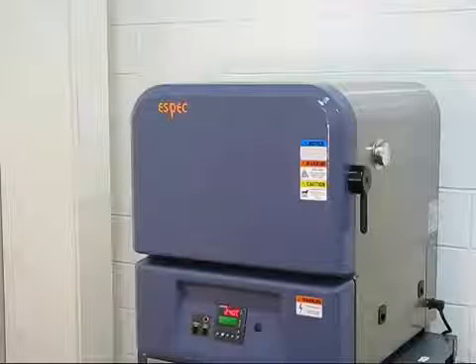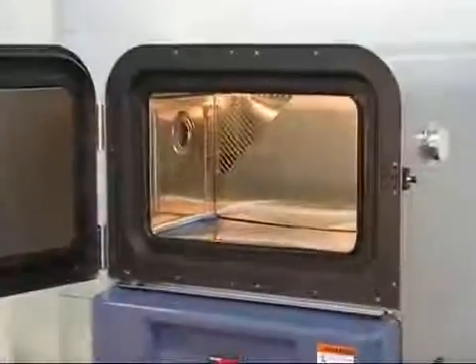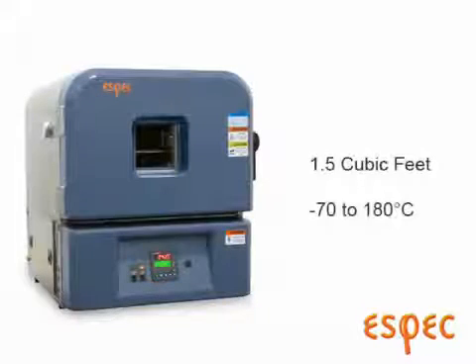ESPEC Criterion Benchtop Chambers for temperature testing your products in hot and cold environments. The Criterion Benchtops have an interior volume of one and a half cubic feet, and a temperature range of minus 70 to 180 degrees Celsius.